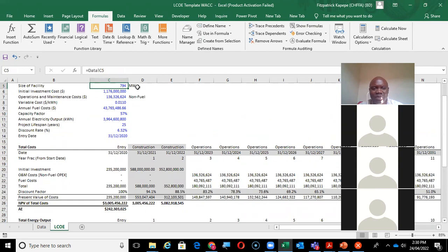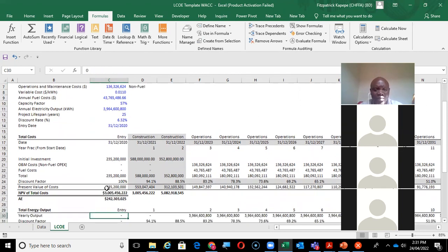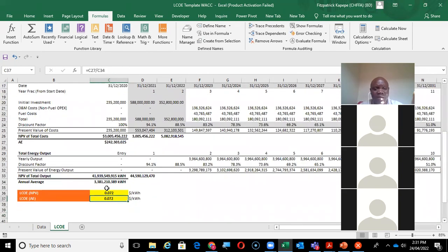Remember what was on this was kilowatt hours. I think if you check the model that I've given you, here it was kilowatt hours, but with the adjustments that I was making in here, it had to go to megawatts. So the numbers that you get there, you need to multiply by 1,000 to convert them from megawatt hours to kilowatt hours, which we have done, giving us the levelized cost of about 7 cents per kilowatt hour.